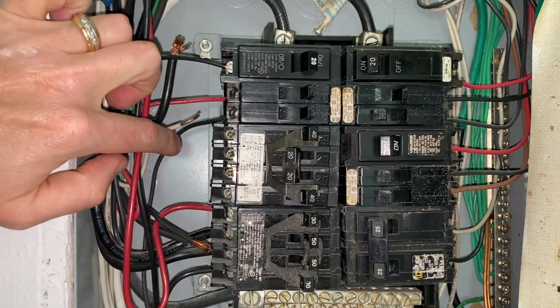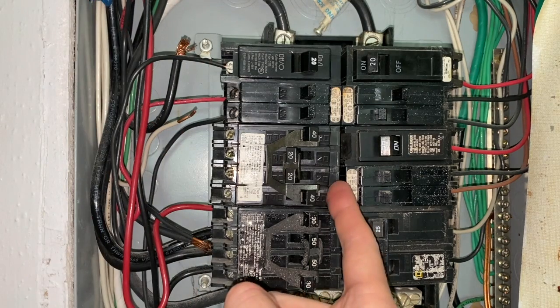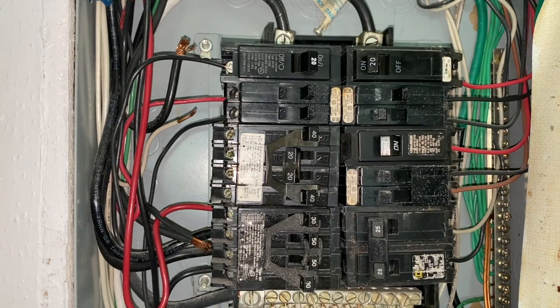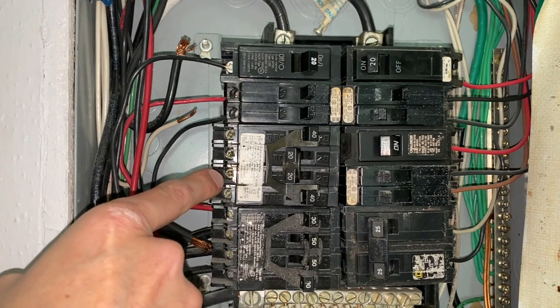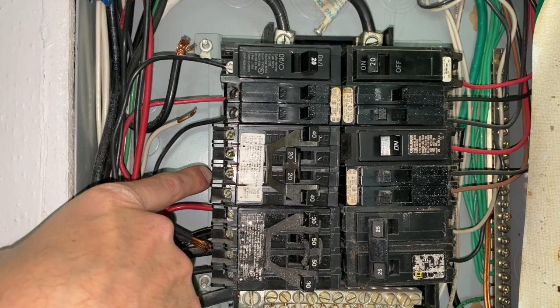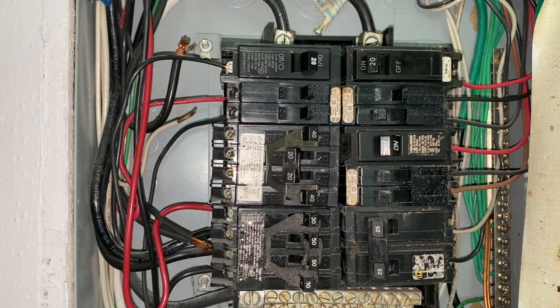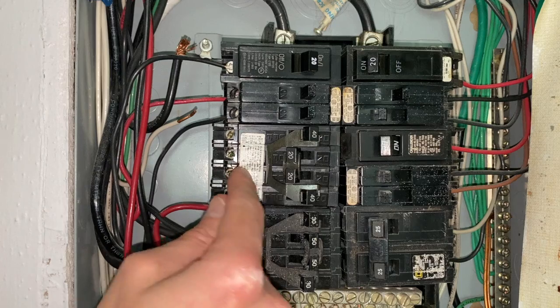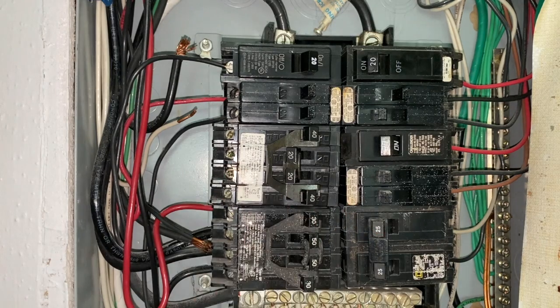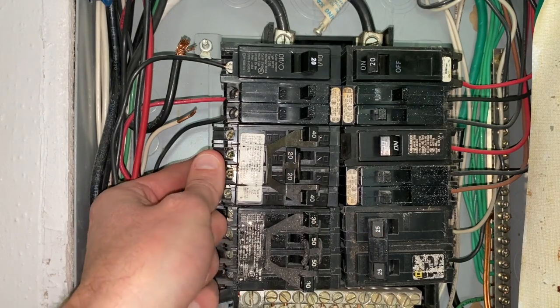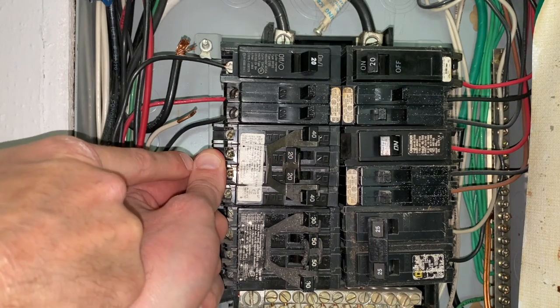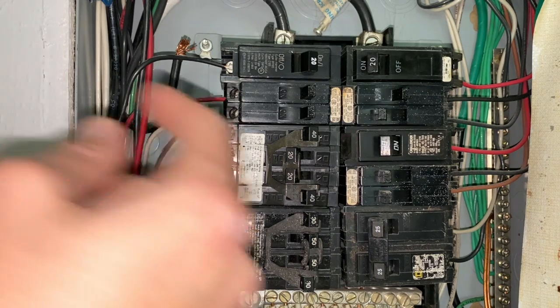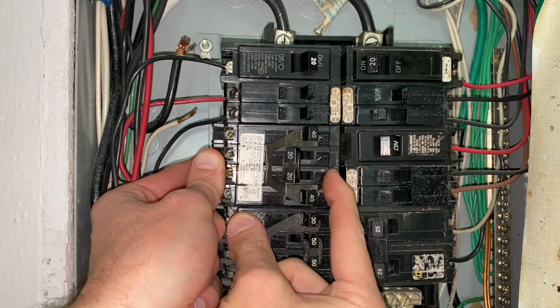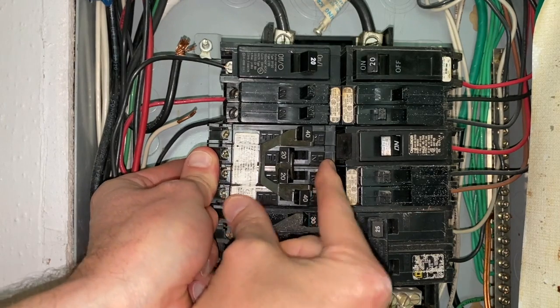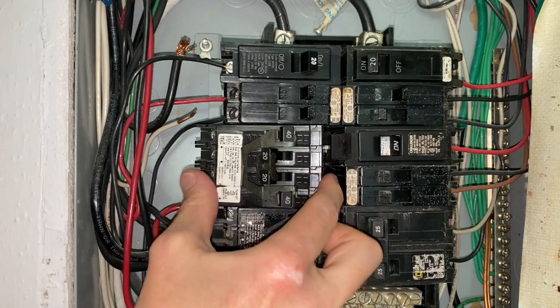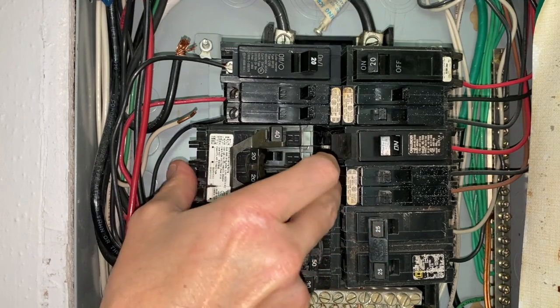As you see there, on the inner side of the bus is where the breaker connects into the electrical contact, and on the outer portion of the breaker is where it loops or clamps in to an inner hook that really has no relation to the electrical power. However, since it's on the left-hand side, we are going to shift it to the left, and I'm going to push in on my thumb to ensure that the portion of the breaker that loops in and around the hook stays in place, and just coming over to the right and pushing it to the left, and pivot it or shift it as shown there. And from here, it should be able to continue to come out.